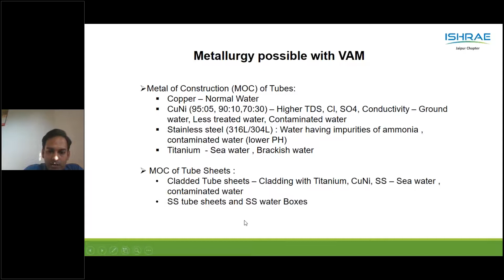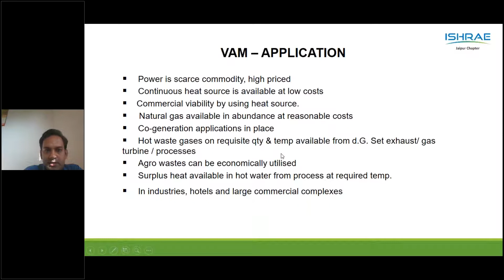These are the metallurgies we are using on the evaporator side or the condenser side: copper, cupronickel for high TDS applications. For a seawater application, we can also use titanium tubes, along with similar metallurgies on the tube sheet. We know VAM applications can be used in plenty of applications where power is scarce or the heat source is available at a very low cost. Further, we will discuss its applications.